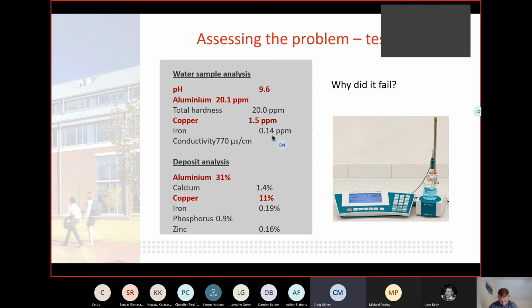When the deposit water was dried out and deposit analysis done, 31% of it was aluminium. So the nice new heat exchangers that were in from the autumn had slowly dissolved and started floating around the system. What's happened then is the aluminium has laid onto the copper, and going back to the corrosion cell, they're dissimilar metals, so they start reacting together. So that's why you've got copper corrosion, and it's all to do with the pH being out on the aluminium.